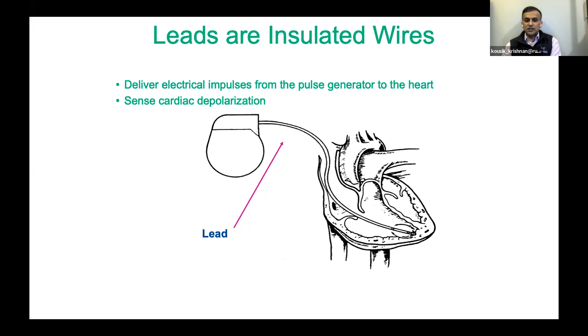There are different kinds of leads. More often than not, these days, we use bipolar leads, and I'll define the differences between those. But there are still going to be some systems that have unipolar pacing leads. They are often a little smaller in diameter because they only need to carry one conductor to the tip of the lead. But they're also going to be prone to more extraneous data that might inhibit pacing. And when you see a pacing spike, you often will see a much larger, more noticeable pacing spike in a unipolar pacing system than you would in a bipolar pacing system.